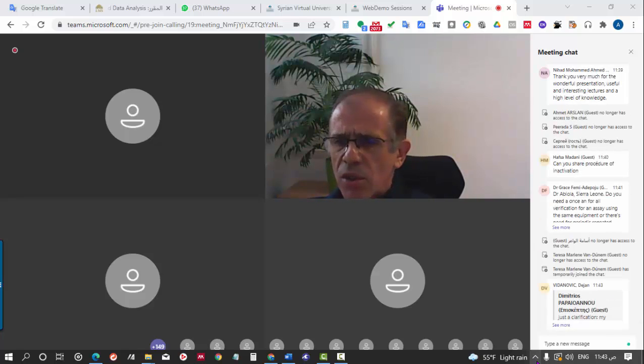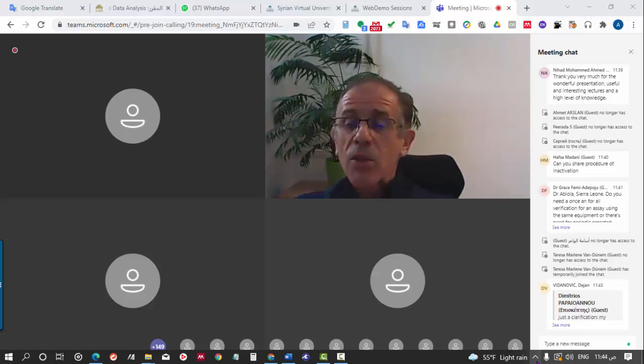And the next question is, do you need once and for all verification for an assay using the same equipment, or is there need for periodic repeat? Well, I would suggest periodically repeating verification. It's not that once you have verified in your laboratory, that's it.